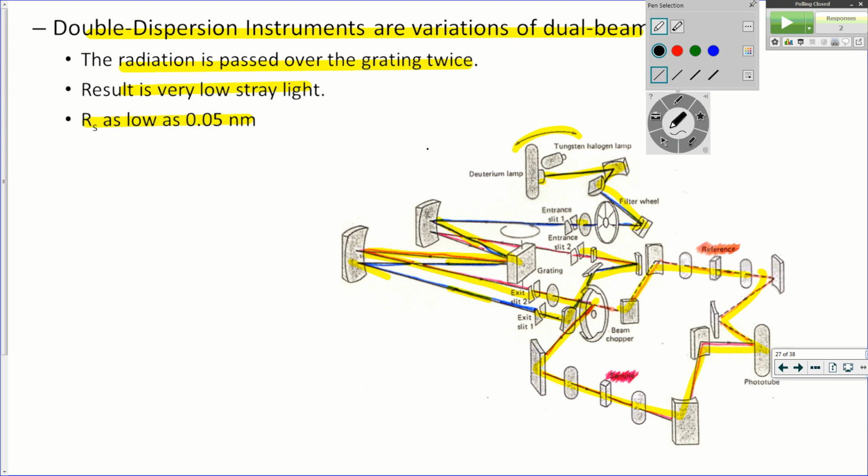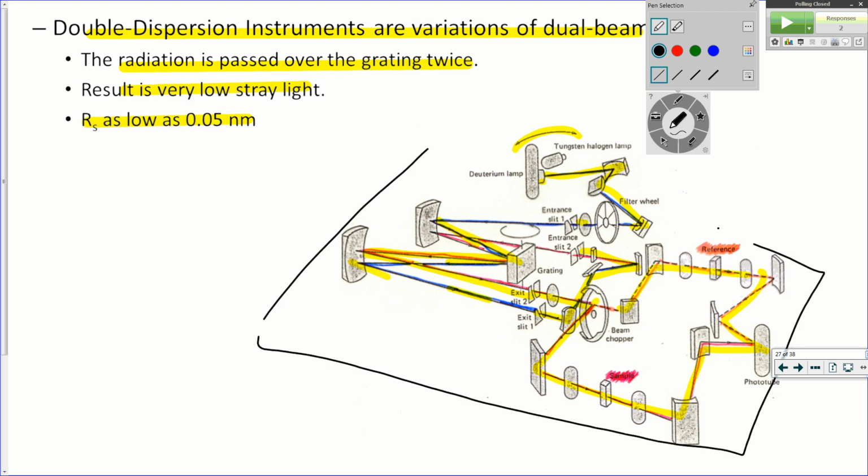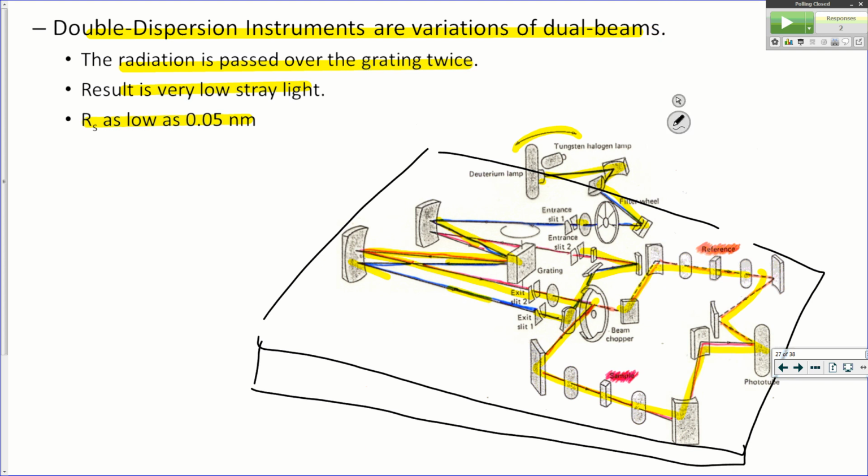So this thing is all going to be sitting on what we call an optical bench, where everything's got to maintain its exact position. An optical bench is typically a big heavy piece of steel with a very low temperature coefficient, so it doesn't expand or contract with changes in temperature. Usually this is beefy, at least a piece of 3/4 inch steel to 1 inch steel on the base. Something like the Shimadzu looks like a small package, and where the photodiode array weighs 15 pounds at the most, the Shimadzu weighs about 150 because of that chunk of steel, that optical bench that it's all mounted to.